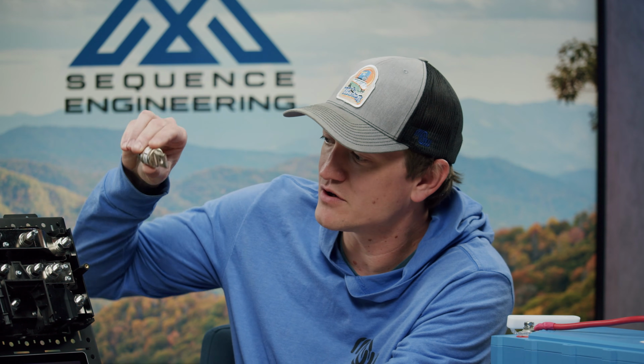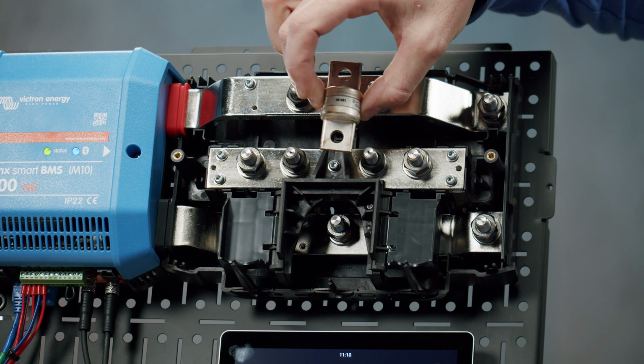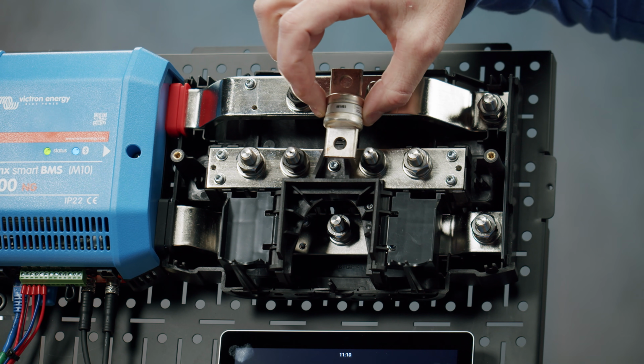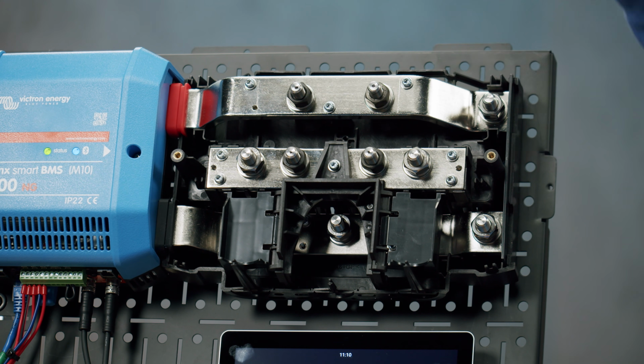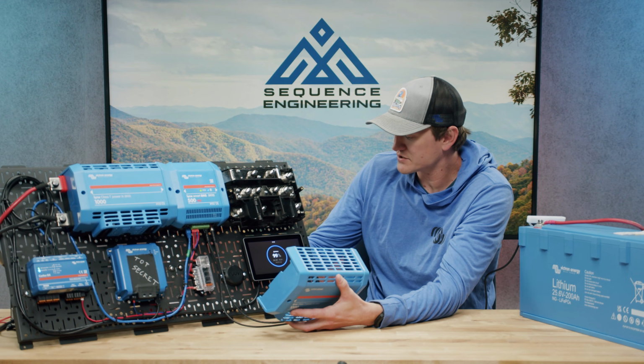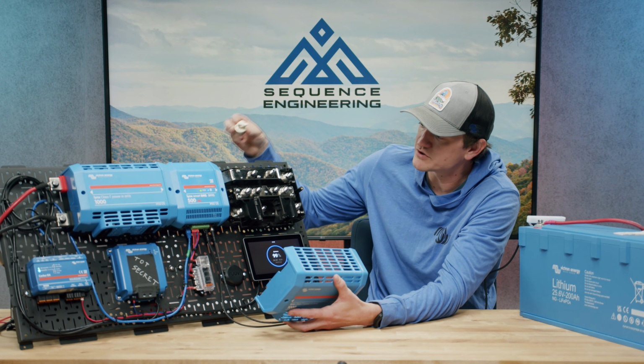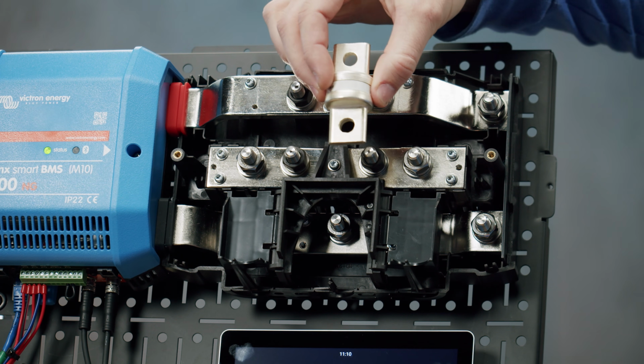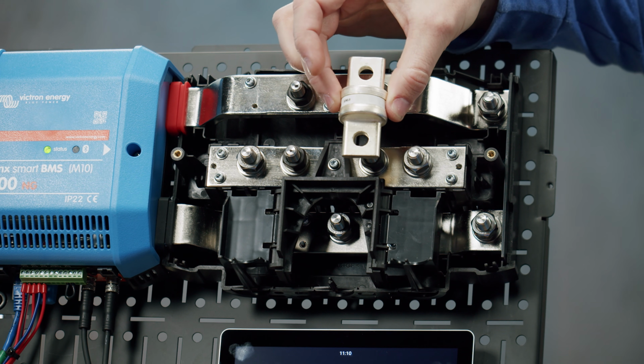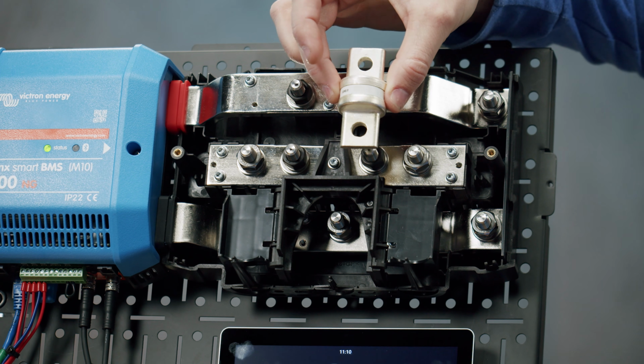Here is an example of a 200 amp fuse, and you'll notice that it's too small to fit across those bolt locations, so that one will not work. You would actually need the larger size, which is, let's say, a 300. You can see the size difference in the bolt hole spacing—that one will fit in there just right.